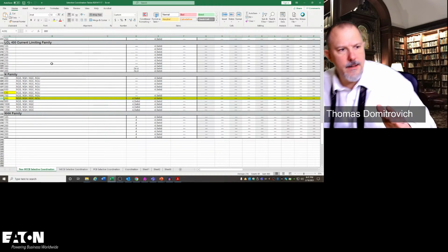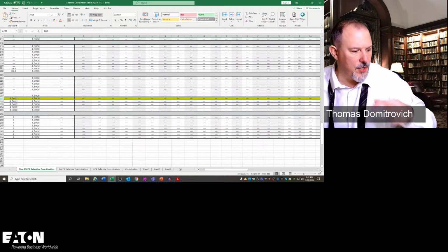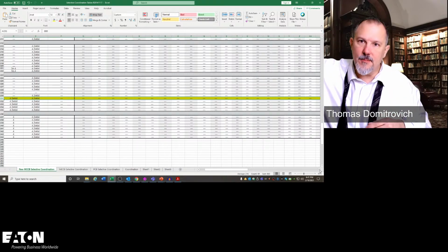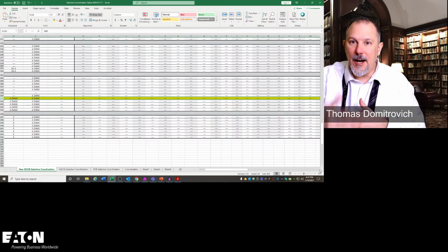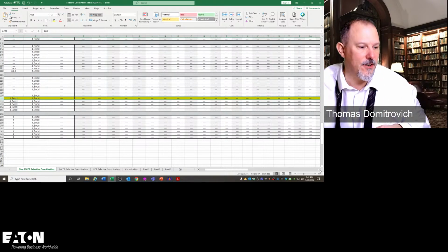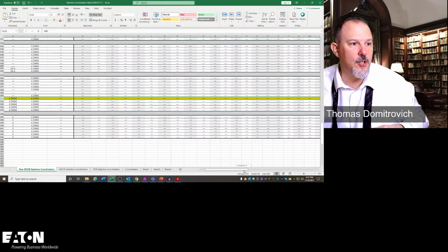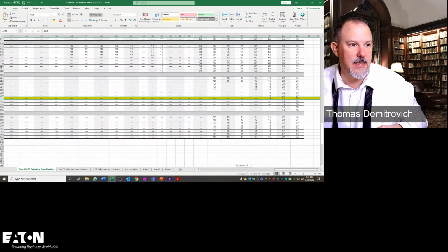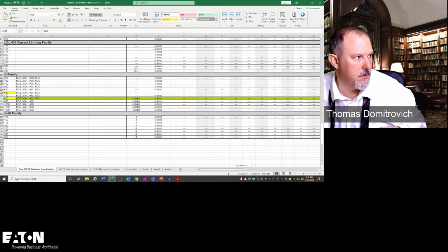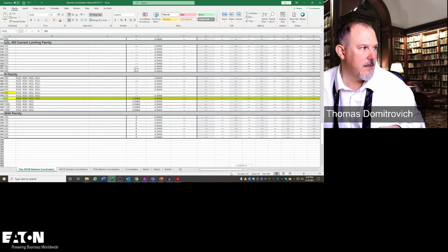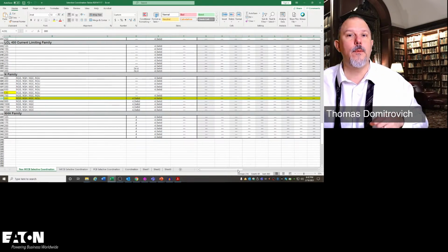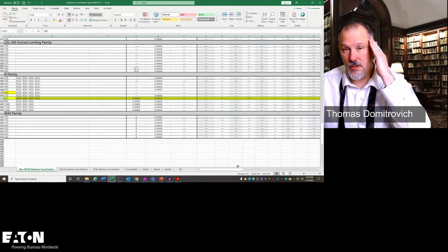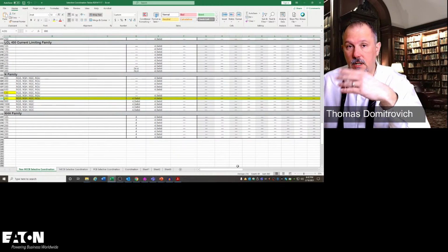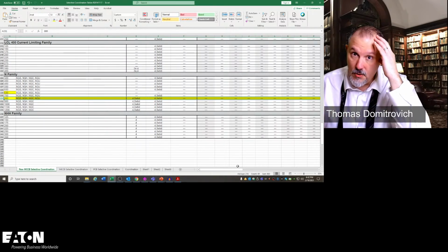I've got to scroll over, not to 12,844, because the upstream device is not going to see 12,844. The upstream device is only going to see 5,566 amps. So I'm going to scroll over until I get to 5,566, which is not on. When voltage changes, you multiply high side by the transformer factor. Yes. It's exactly right. Wait a second. I transpose my secondary current because remember, I did my math. I know what my fault current is going to be on the secondary, and I would transpose that to the primary.